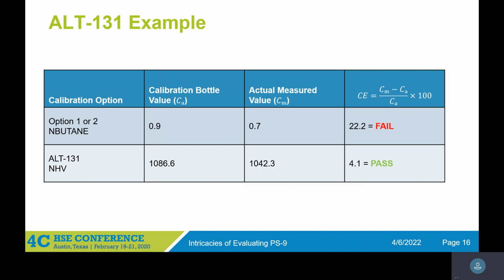Just looking at two examples here, a lot of the heavier components, the butanes and pentanes, in these cylinder gases were at very low concentrations, like in the 0.9, 0.7 range. So slight differences in there, since we're using the calibration standard as our point of reference for calculating error, the smaller concentration ones were resulting in fails of just being a couple decimal positions off. Whereas with the net heating value, you can be off by tens and still be within the tolerances.